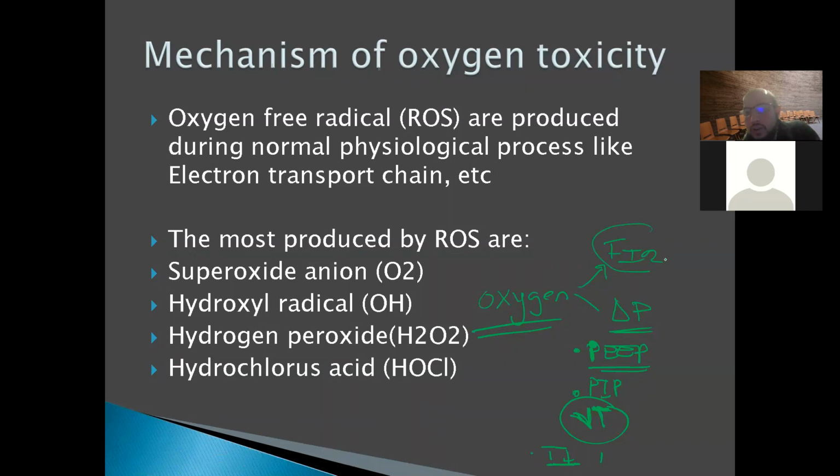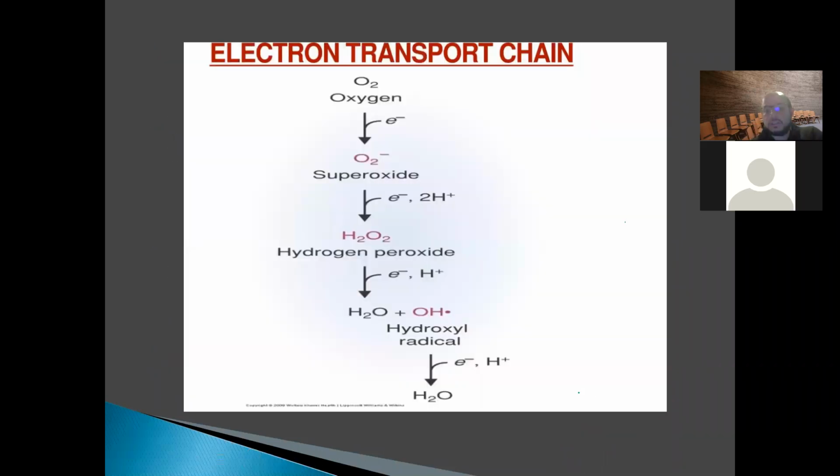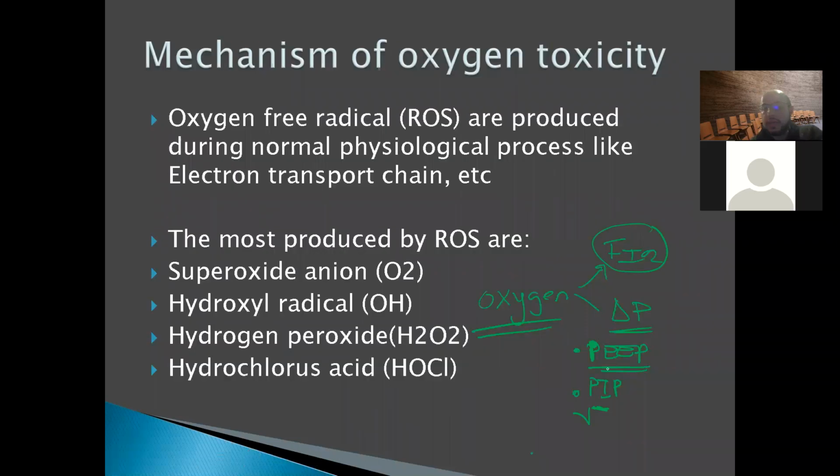For the FiO2 part, it's very important. That's usually controlled by the nurse, correct? You set the saturation goal for the baby. For example, I need my saturation to be 89 to 92 percent, just as an example. So the nurse controls the FiO2. We have something called the blender. I realized that in Libya there's no blender there. The blender is where you control how much oxygen.